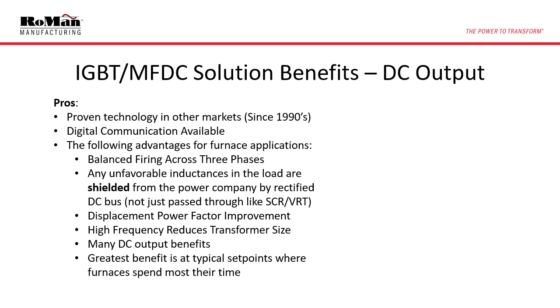IGBT MFDC technology has been used in other markets since 1990. There are multiple forms of communication available. IGBT MFDC is balanced across 3 phases. Any avoidable or unfavorable inductance in the load will be shielded within the control. The displacement power factor remains near unity at all practical operating ranges. The high frequency output of the inverter allows us to use smaller transformers. The direct current output mitigates reactance and also produces more efficient heating. The best part is that all of these benefits are present at typical operating ranges, unlike with SCR and VRT controls.